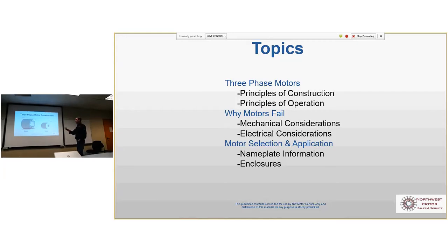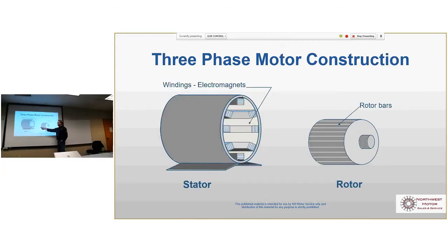So these are the two basic components of a motor. You've got the stator and the winding, or the rotor. Inside the stator is electromagnets, which we're going to talk a little bit about how that's done in here. And then the rotor bars are the corresponding element in the motor that works with the windings over here to induce magnetic torque into the rotor.